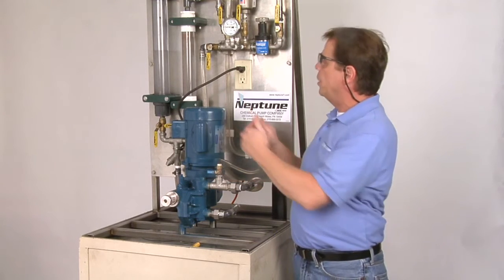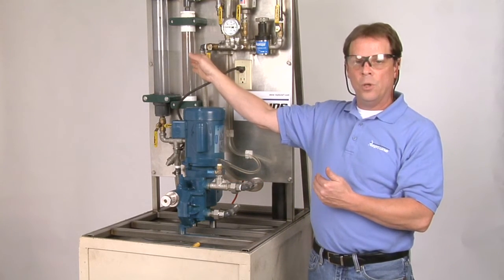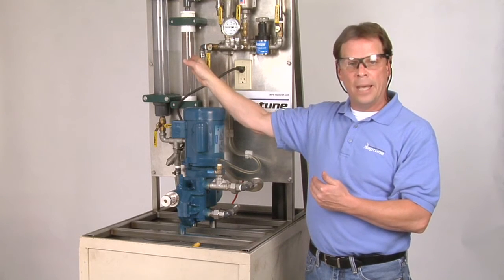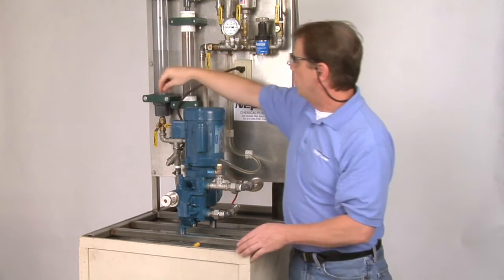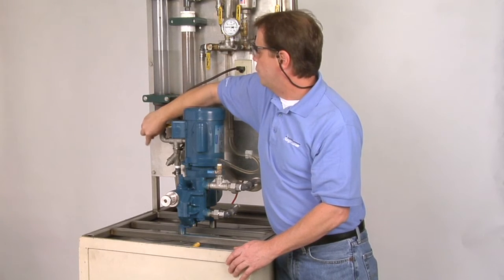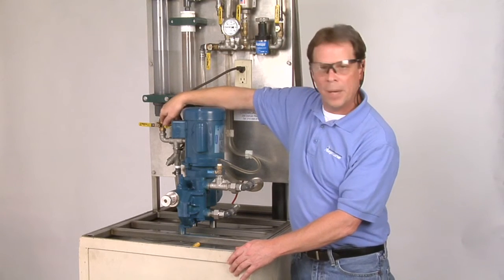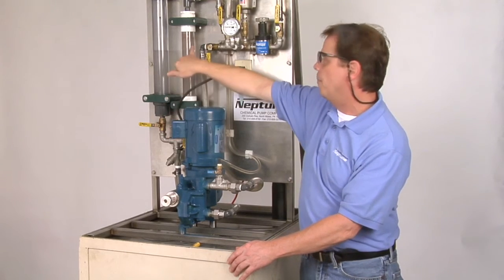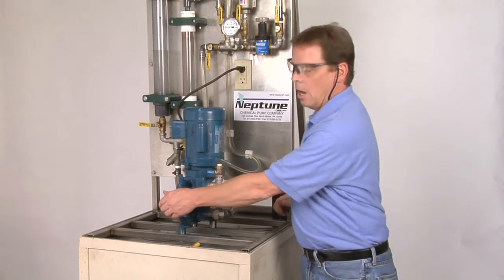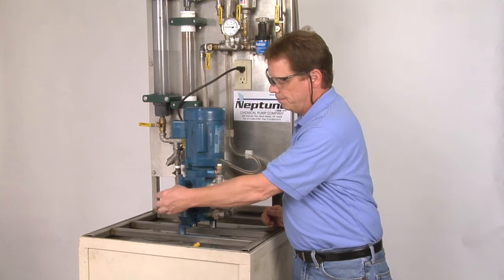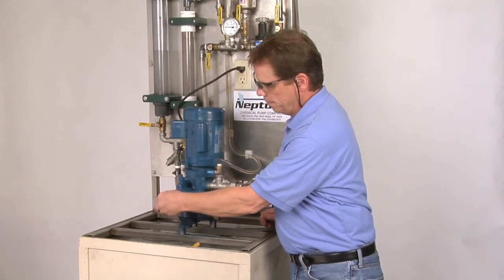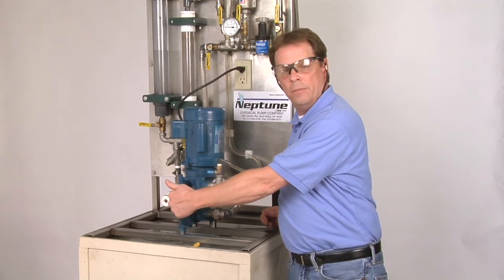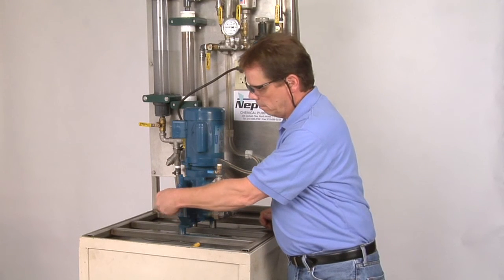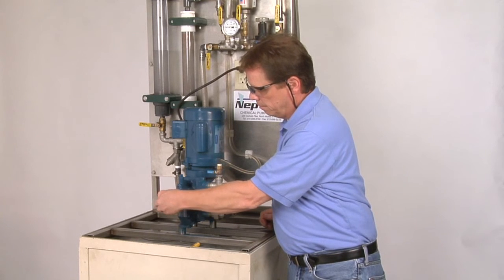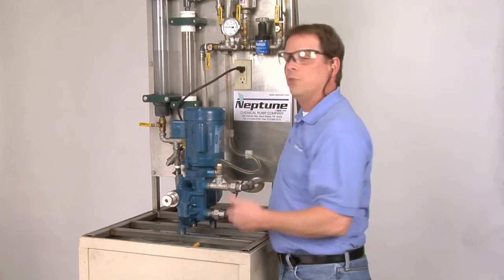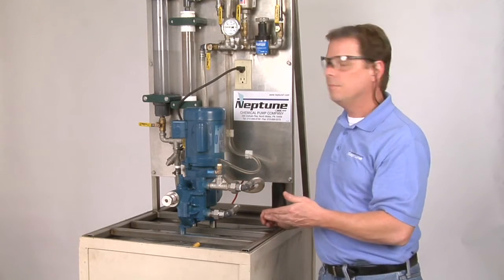And if you have a calibration column, and in this case we do, we're going to see the flow coming down in the pump. So what I'm going to do is shut my supply off, open up my calibration column, and now we're going to pump through the column. I'm going to go up to 30% stroke. One full rotation is 10% of the flow. Now we'll typically let that sit for 5 minutes.